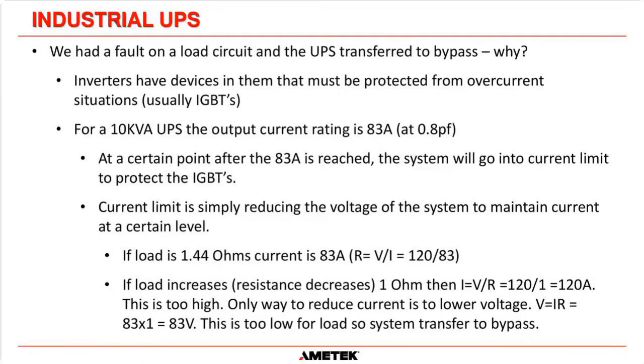We had a fault on a load circuit and the UPS transferred to bypass. Why did it do that? Okay. I'm going to try and take this a little bit slowly. Inverters have devices inside of them that must be protected from overcurrent situations. And the power switch of choice in nearly all UPSs these days is an IGBT, which is an insulated gate bipolar transistor. Okay. The thing about IGBTs is they are very sensitive to overcurrent situations.